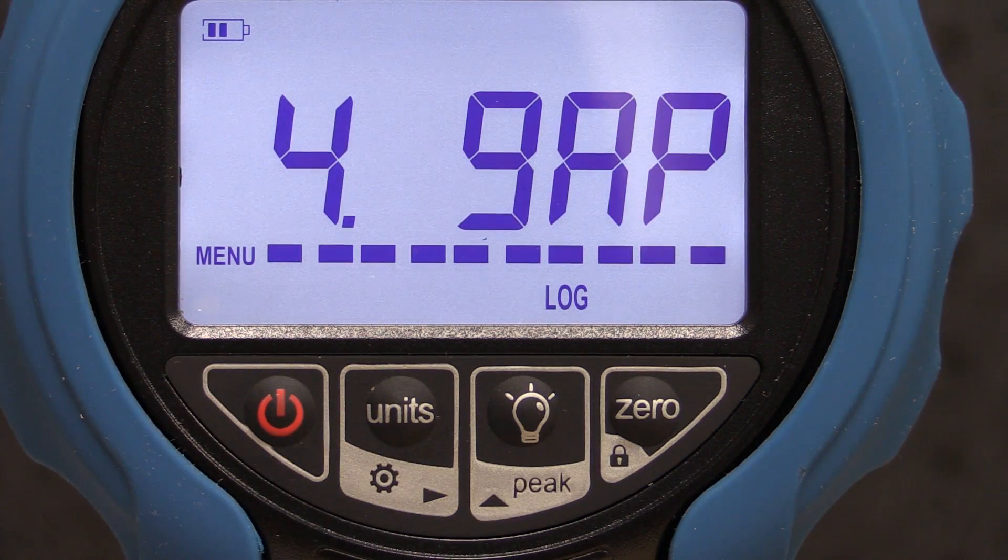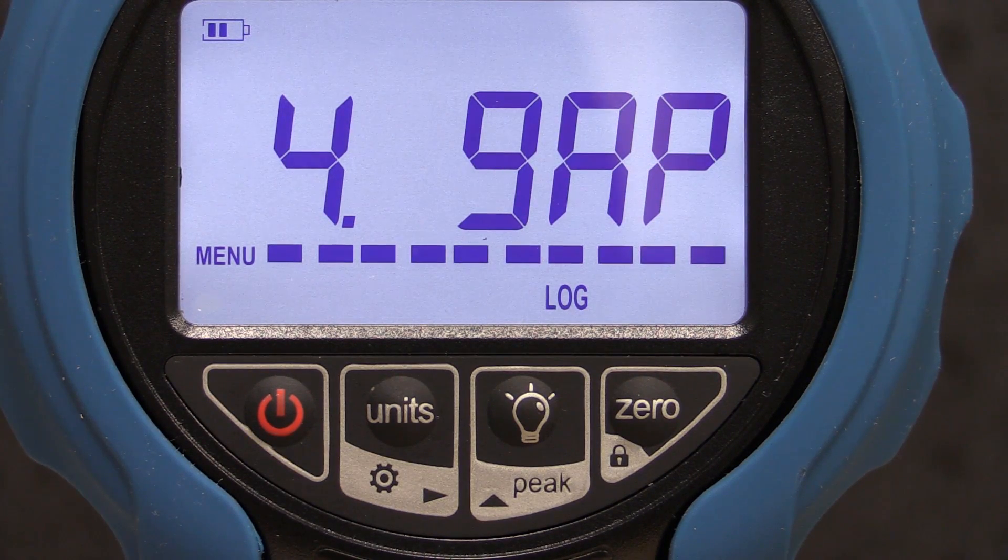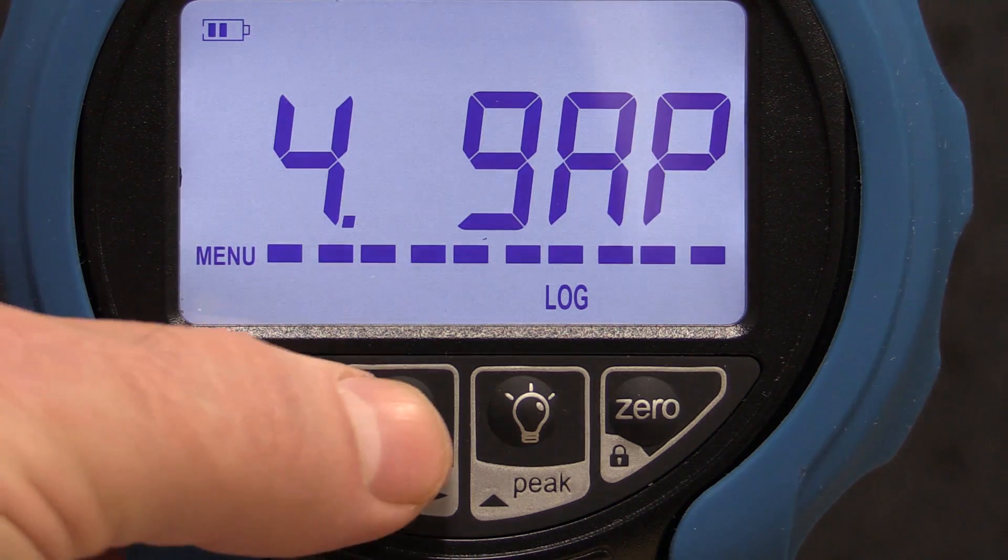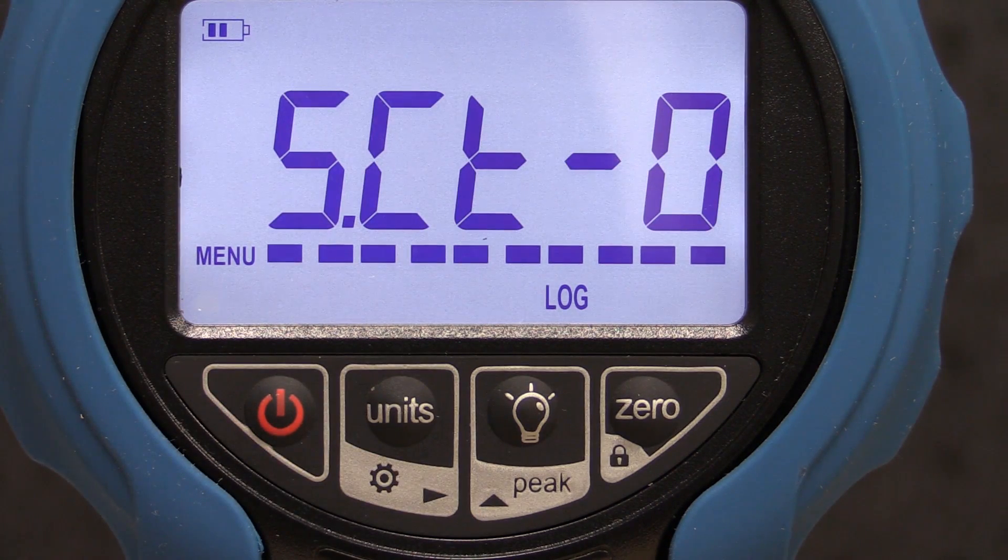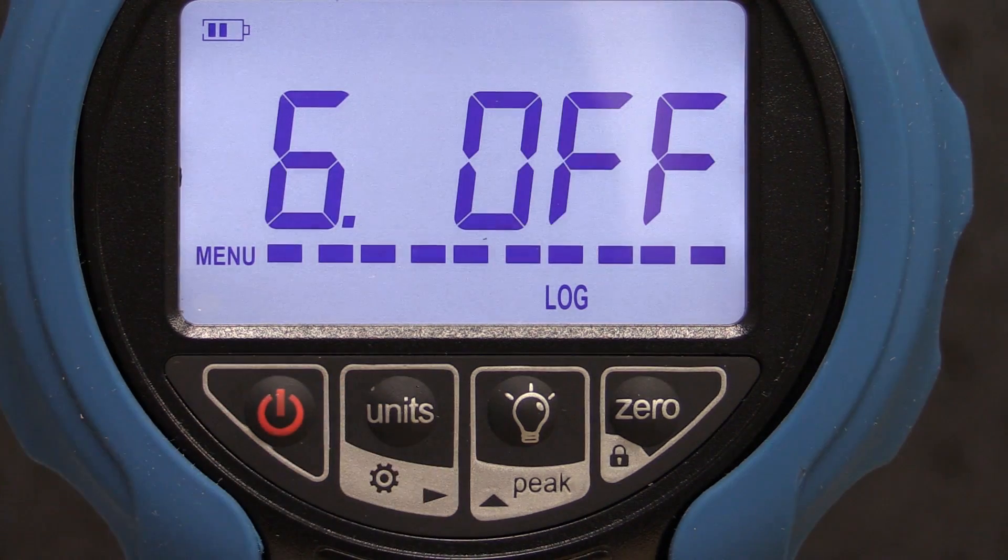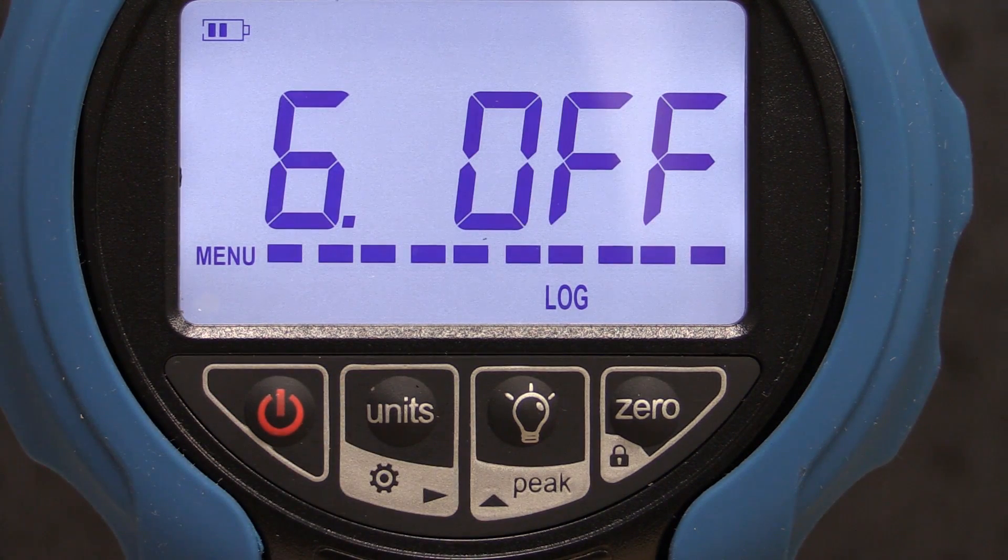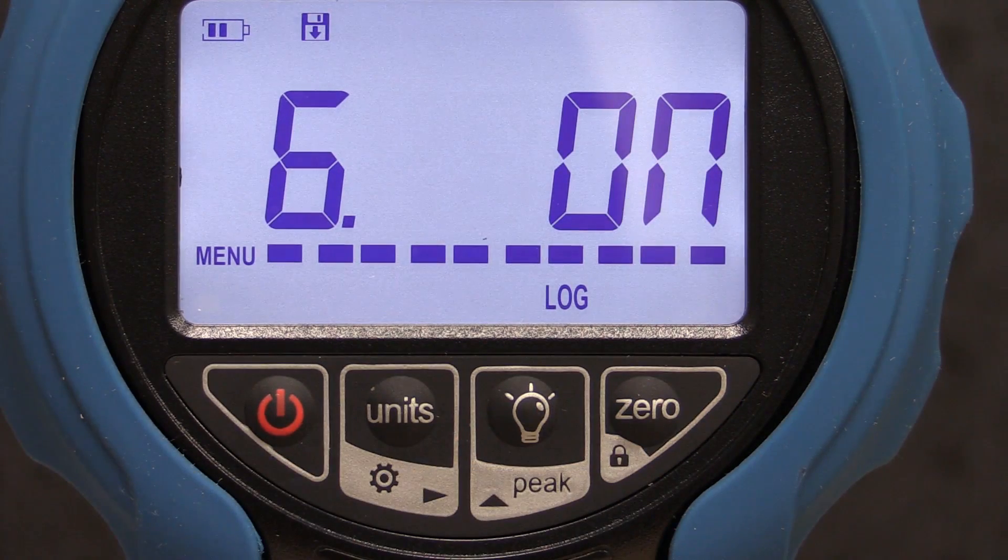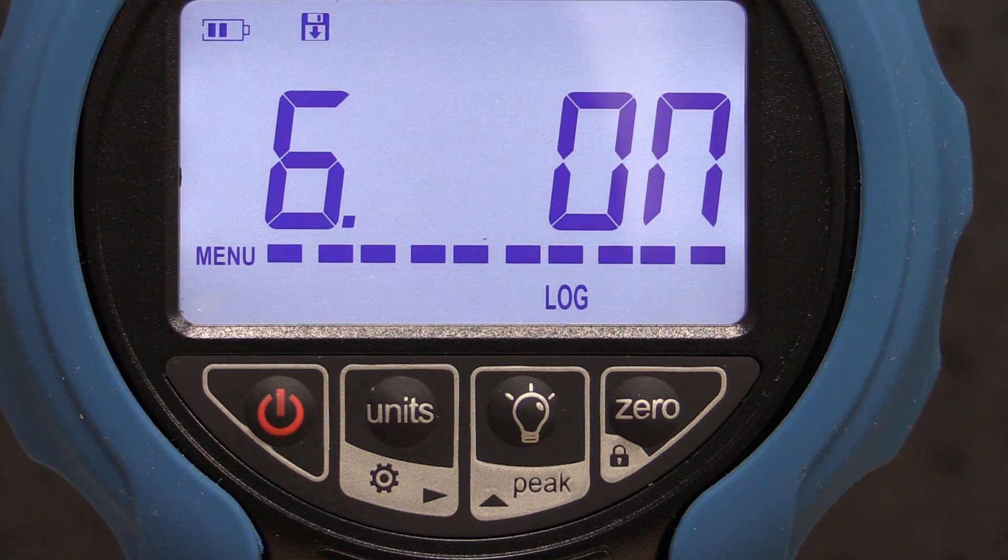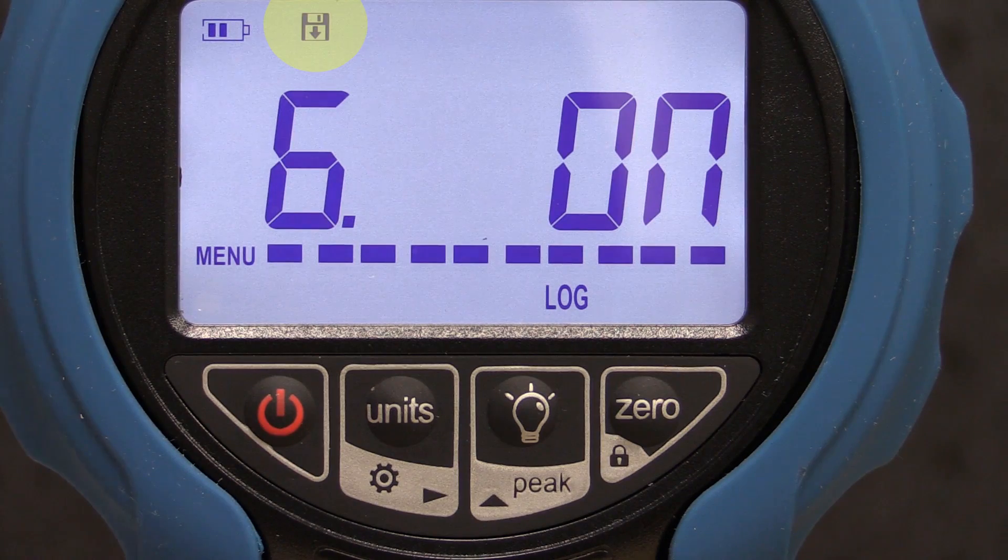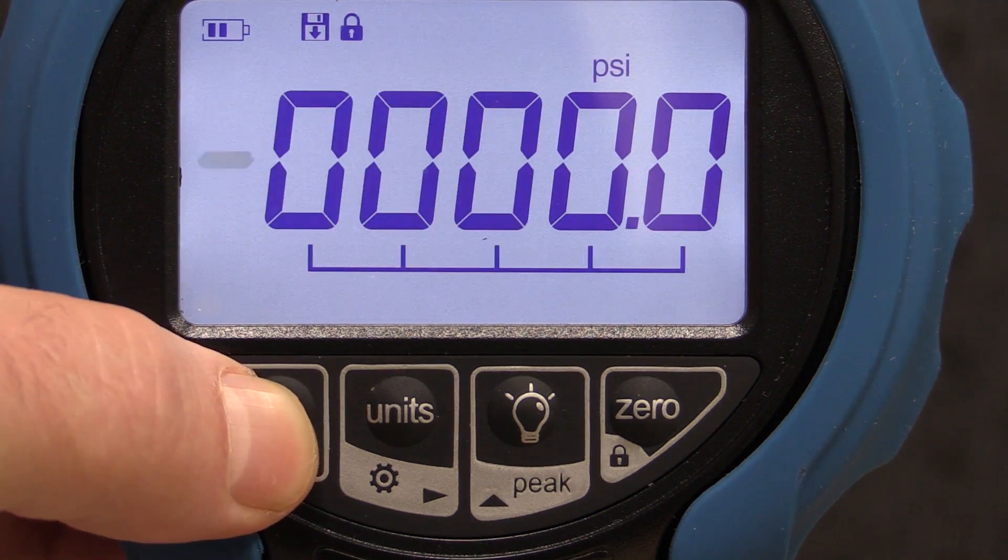The fourth menu, GAP, sets the data logging interval in seconds. The fifth menu is the data logging default setting for power up. And the last menu is the enabling or disabling of the log function. By pressing zero, the log status will change from off to on and the logging icon in the top corner of the display will appear. Press the power key to return to the main display.